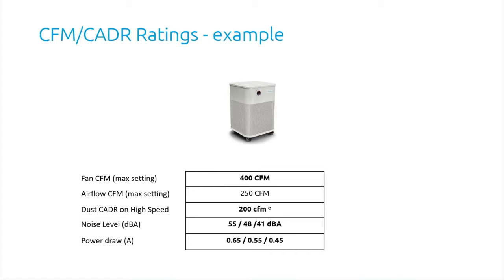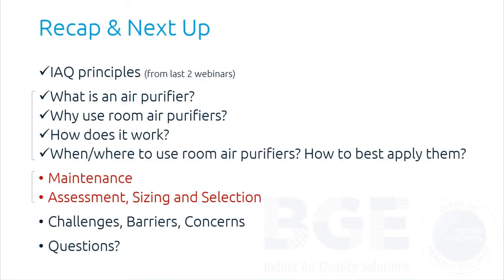Yeah, exactly, and you got it. So the fan setting at 400 is just the bare fan. You take the fan out, you put it on a desk and you test it, and it can pass 400 through. Now you put it in the unit and you add a HEPA filter. The reason a HEPA filter works so well is because it stops things, so it adds a lot of resistance into the airflow. Every time you add a HEPA filter to a fan, you're going to lower that airflow. Yeah, I've always thought that's a silly spec to even publish. Who would ever run that thing without filters inside it, right?